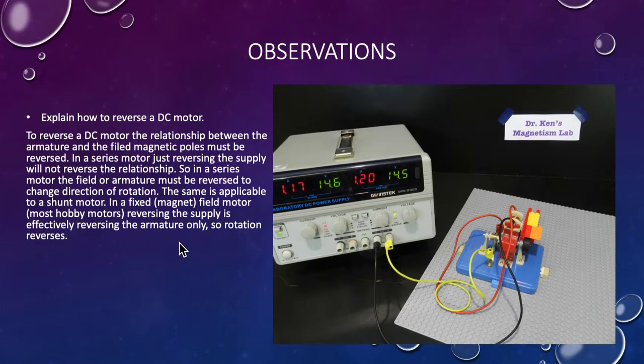Explain how to reverse a DC motor. To reverse a DC motor, the relationship between the armature and the field magnetic poles must be reversed. In a series motor, just reversing the supply will not reverse the relationship. In a series motor, the field or the armature must be reversed to change the direction of the rotation. The same is applicable to a shunt. In a fixed magnet field motor that most hobbyists use, reversing the supply is effectively reversing the armature only. So the field doesn't get reversed, so you get reverse rotation.